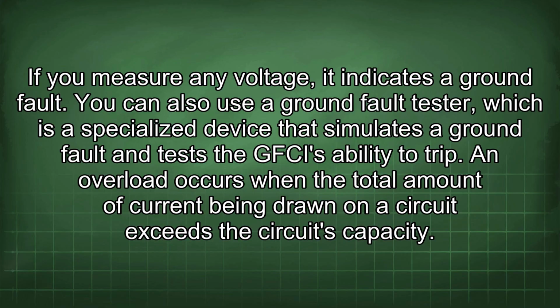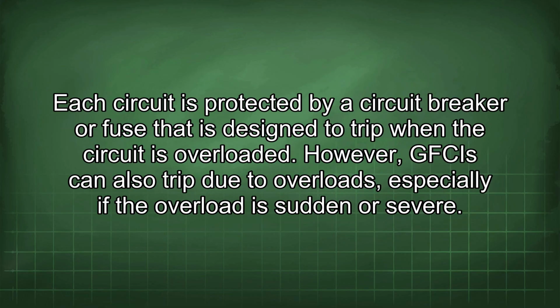An overload occurs when the total amount of current being drawn on a circuit exceeds the circuit's capacity. Each circuit is protected by a circuit breaker or fuse that is designed to trip when the circuit is overloaded. However, GFCIs can also trip due to overloads, especially if the overload is sudden or severe.